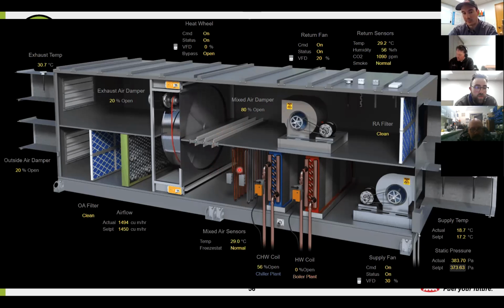And now we're going to pass through our mixed air sensors. This is just detecting what the temperature of the air is. And there's also a freeze stat here. So when we had our cold snap, we need to see if the air is way too cold and we're starting to freeze, we need to start closing down our outside air, or alarm that we could be running into a freezing situation where we'll burst coils, things like that. But that air then goes down through here, through the mixed air sensors.